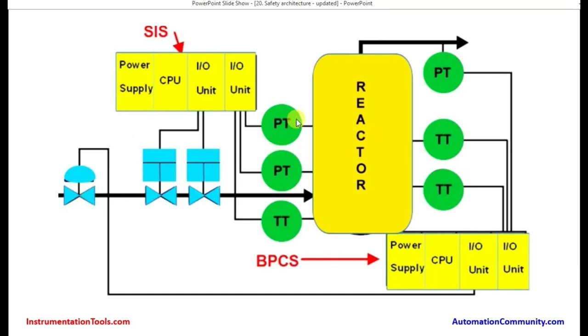Similarly, another set of pressure transmitter and temperature transmitter is going to the input-output module of the safety instrumented system. This is a different system — an altogether different processor — because the safety instrumented system requires a very high level of testing and proofing. The processor itself may be different — it should be different, having high capacity and high processing speed — and it could be a redundant processor.